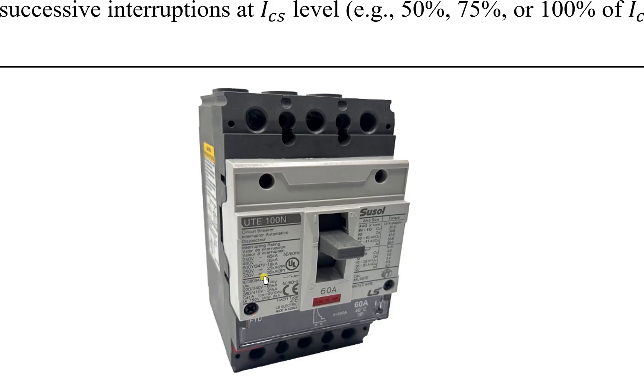Looking at another circuit breaker labeled IEC 60947-2 for industrial applications, you can see the ICU value depends on the voltage level: for example, 65 kilo-ampere at one voltage range and 35 kilo-ampere at another. Notably, the service breaking capacity ICS is 100% of ICU in this case, which means this breaker is designed to interrupt the full ICU fault current several times.